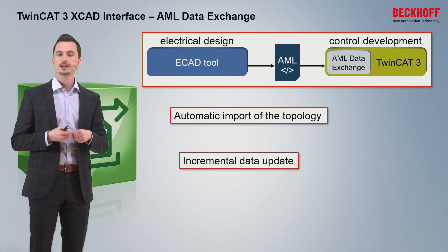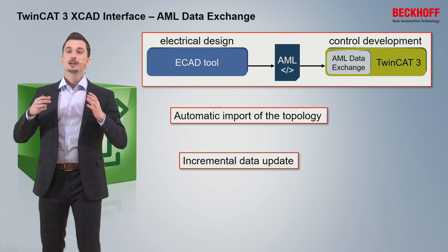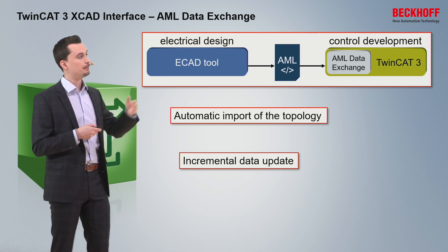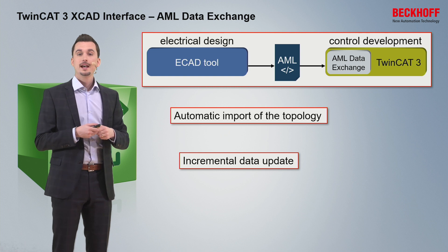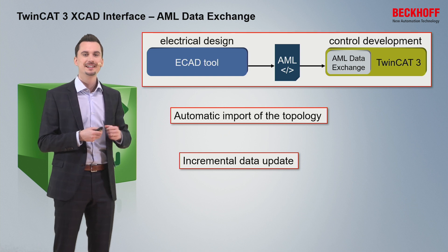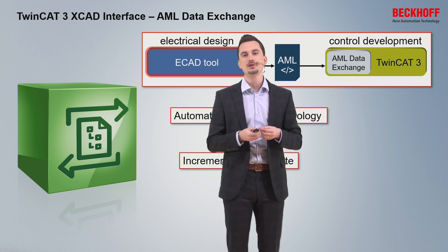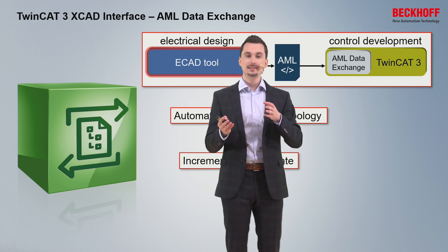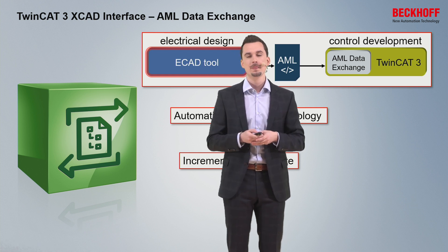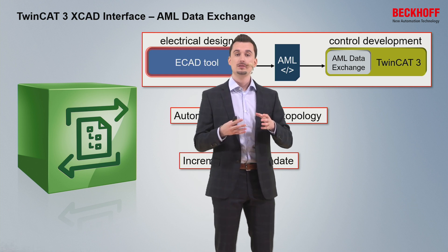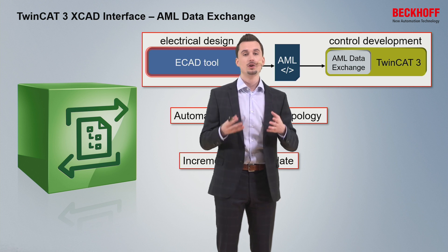So if we are in an early phase of the project, we can more or less parallelize the electrical design and the control development. We can export an early version of the IO topology and import it into TwinCAT 3, then continue working on both sides. When a second version of the IO topology is ready on the ECAD tool side, we can import it into TwinCAT 3, and the TwinCAT project compare tool is automatically started — enabling you to easily merge and compare the existing IO topology with the one being imported. Even if you have made changes to the existing IO topology in TwinCAT 3, you can save those changes and only import new or changed content.